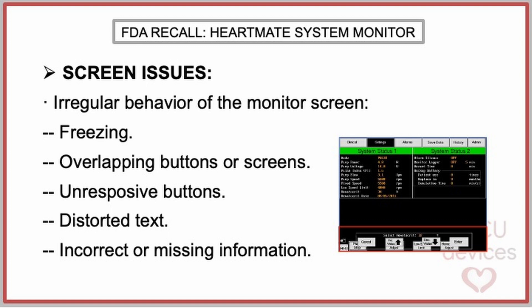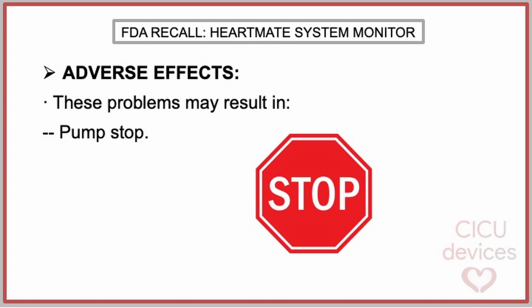These problems can lead a clinician to unintentionally change pump settings or press the pump stop button. Using the affected product may result in serious adverse effects such as pump stop. If the stop pump button is accidentally pressed due to display issues, the pump will pause momentarily and restart unless the button is held for more than 10 seconds. In that case, the pump will stop and the controller will issue a pump off alarm. Press any button on the controller to try restarting the pump and resolve the pump off alarm as per the instructions for use.